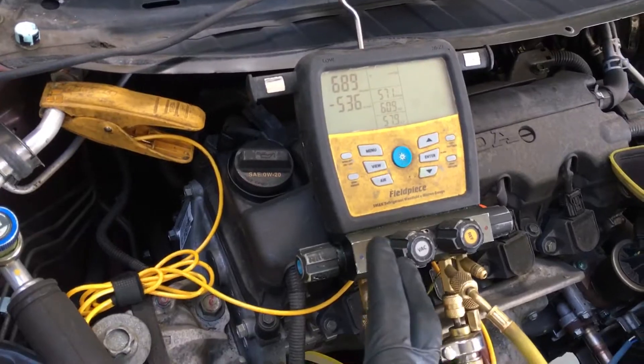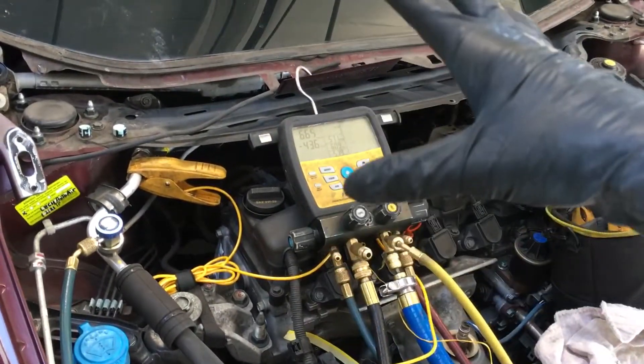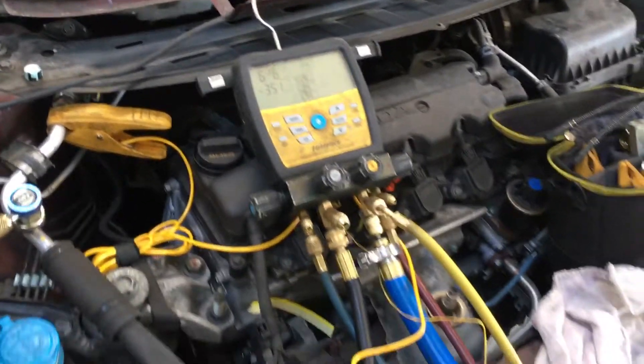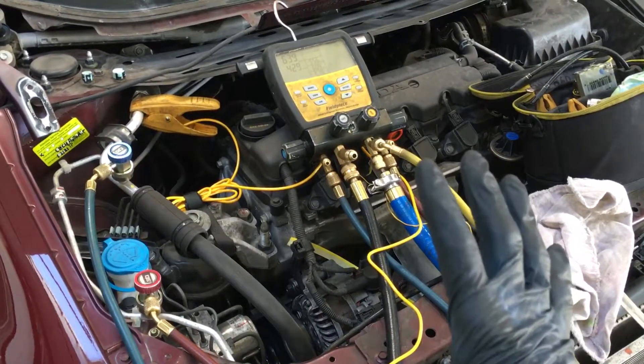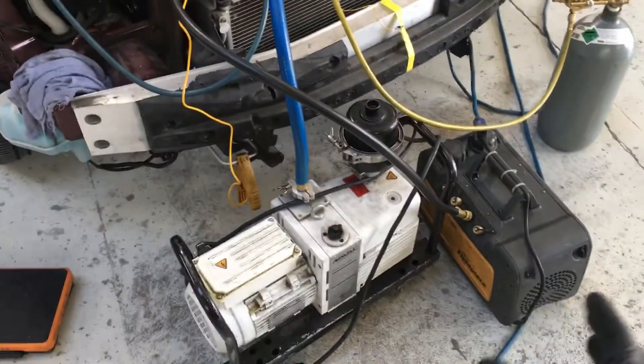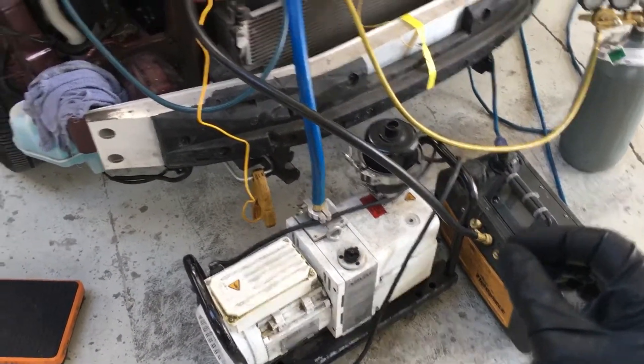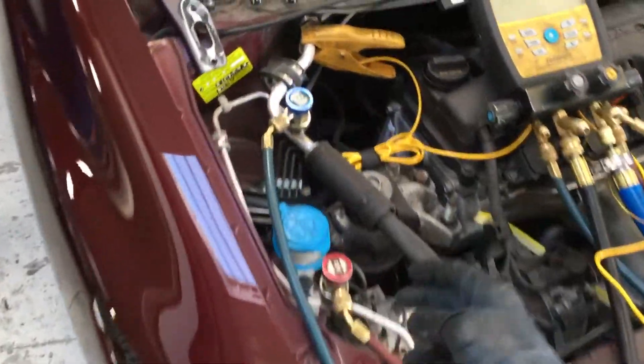It's going down. I just opened it up because I was checking the rate of decay and how much moisture was in the system — it went up about 900 microns. Now, I've had people say more vacuum pumps make no difference because it maxes out at the restriction, depending on your valves. Yes, that is true up to a certain point.